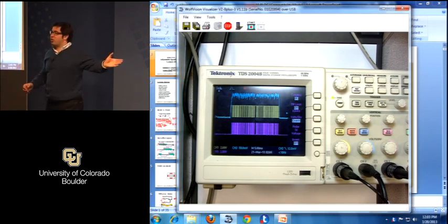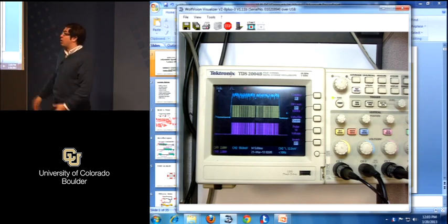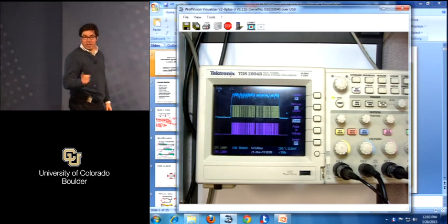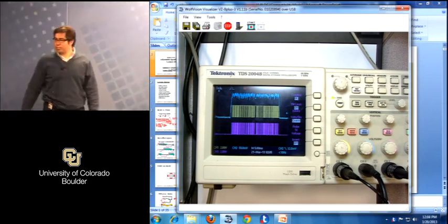And that's how you essentially, you saw that on that torque speed graph. You essentially don't have high torque capability, but you can increase the speed significantly. You don't have torque capability just because your torque is current times back EMF, and if your back EMF is not maximum, you're not going to get the rated torque. It's logical, right? So you're not going to get really high torque performance, but speed-wise, you can significantly increase the speed of the drive. Okay? Any other questions? Good enough?